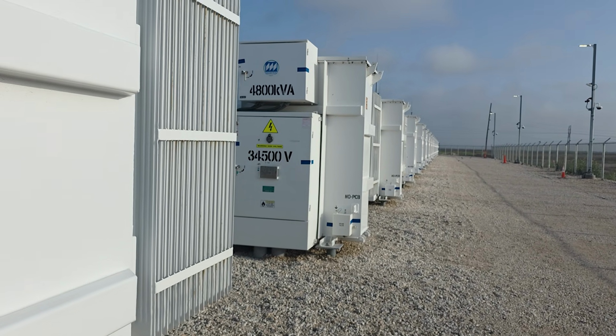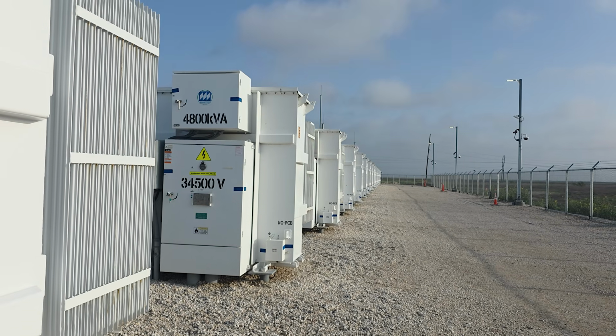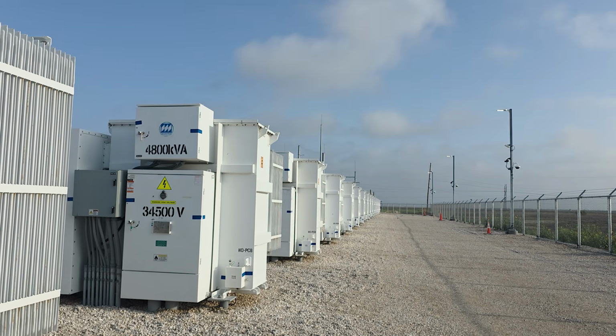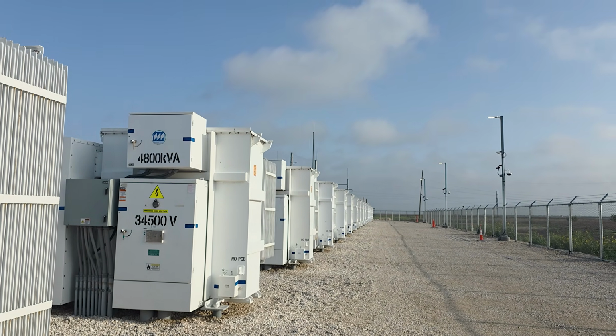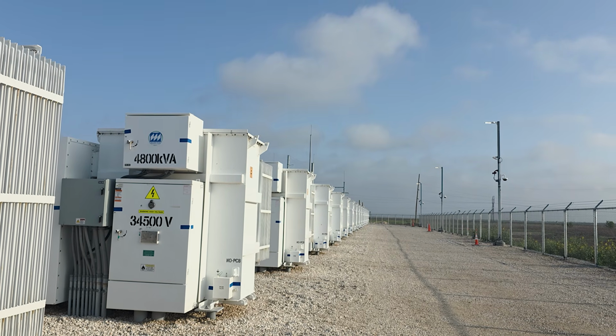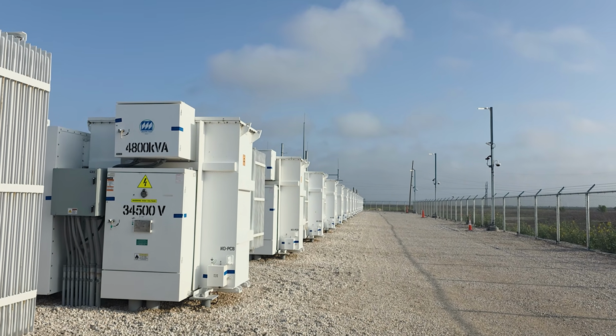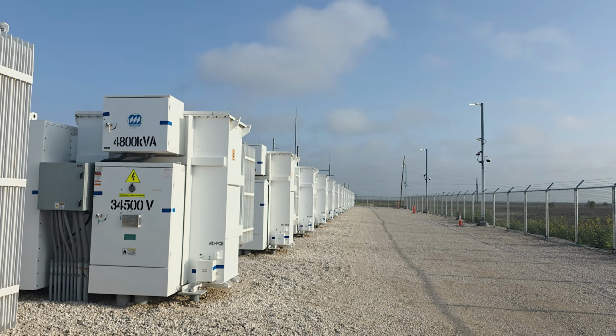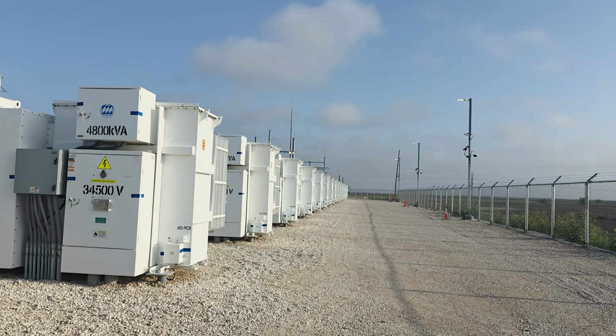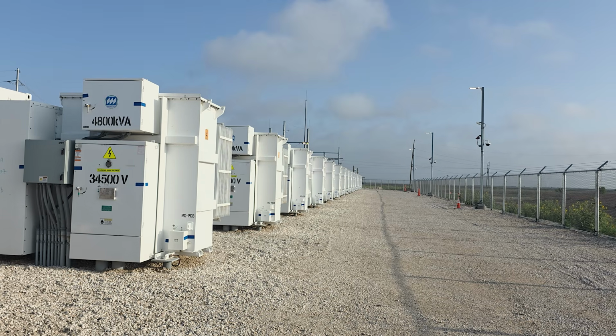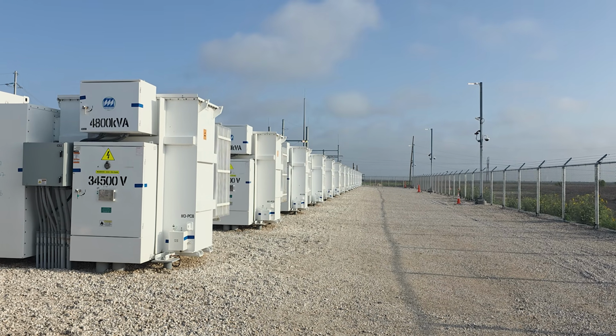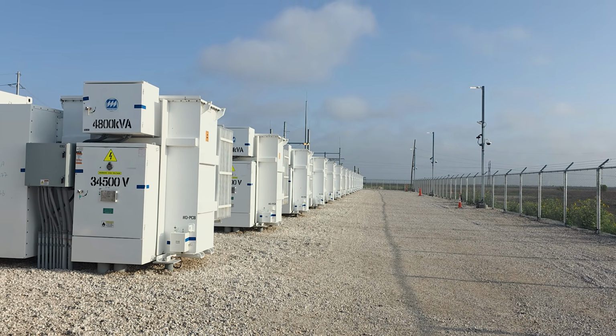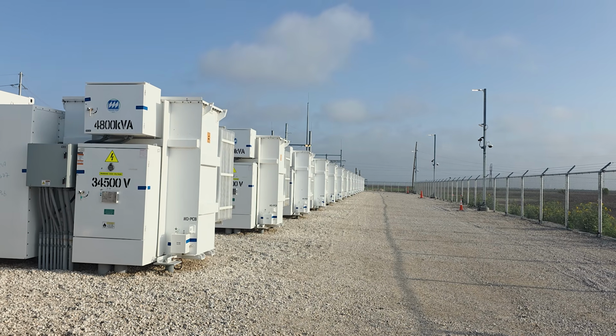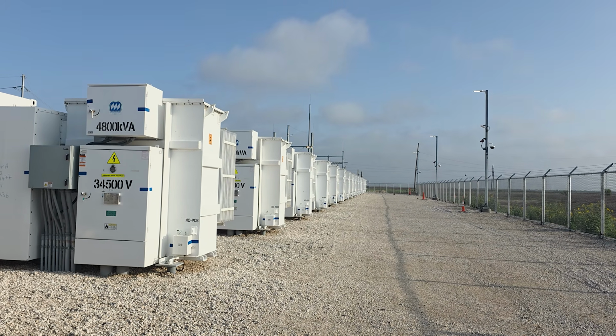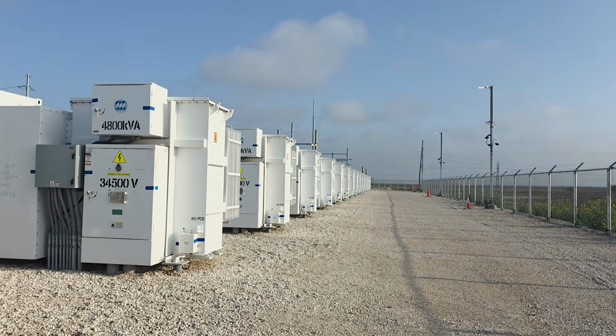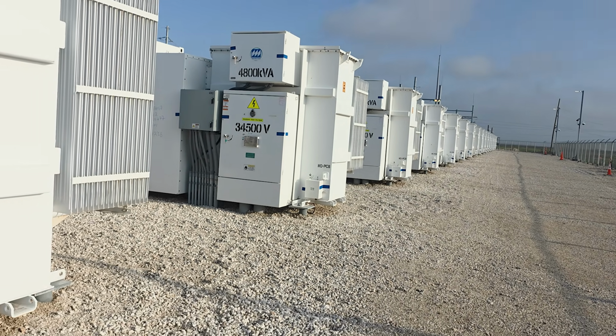I'll get into transformers next, but you can see the line of them. So from the substation, which is down there on the other side, we've got a number of feeders, and I think there's three or four on this row. And what they'll do is they'll pop up to, say, the first transformer down there. Then they will daisy chain from transformer to transformer and gather up that power from each transformer. And once you hit the maximum rating of that cable, then that's where the next home run starts. And then it goes into another 4 or 5 transformers. Then the next one starts. The next one starts until you get to the very end.